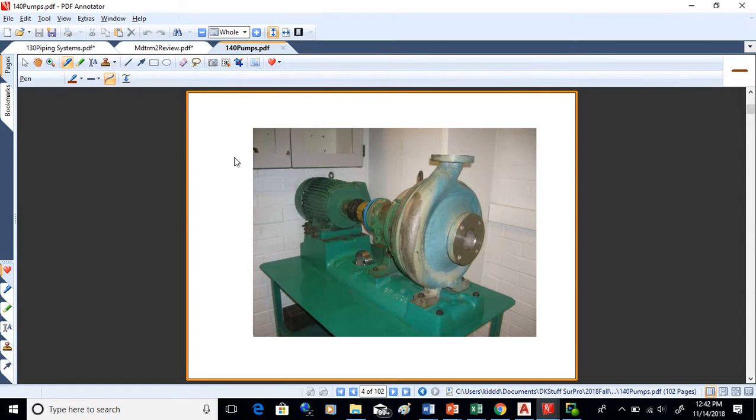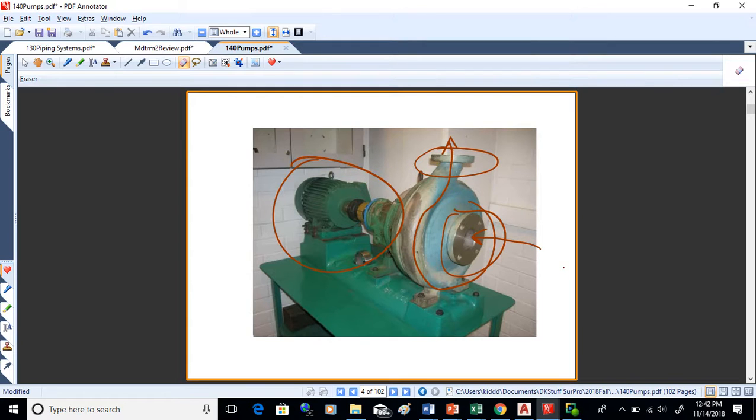Here's a picture of a centrifugal pump. You're looking at the volute - you can see the main channel for the water as it comes around and out. Water comes in, gets caught by the impeller, thrown into the volute, and basically thrown up through the top and out into the piping system. You can see the flange where you connect the pipe, the inlet flange, the motor and shaft coming through. You need some seals so that shaft will spin without leaking water.